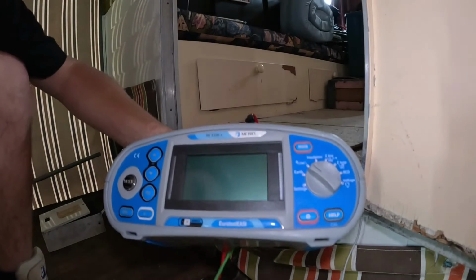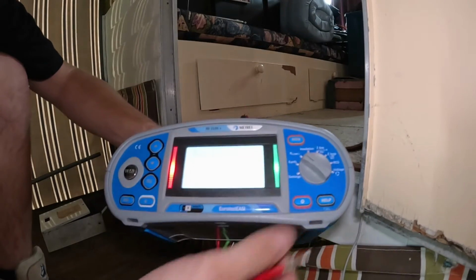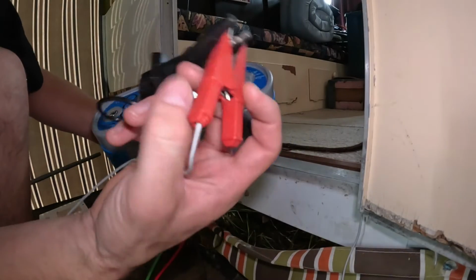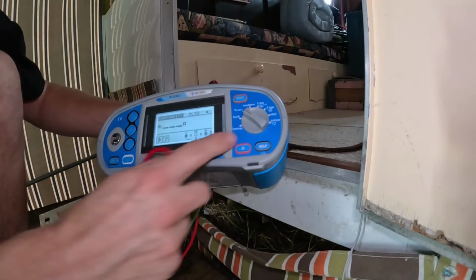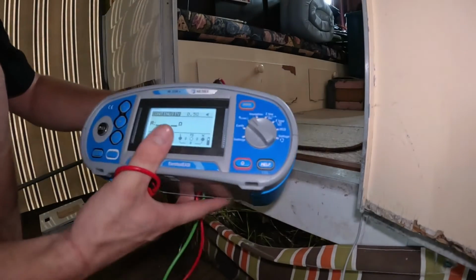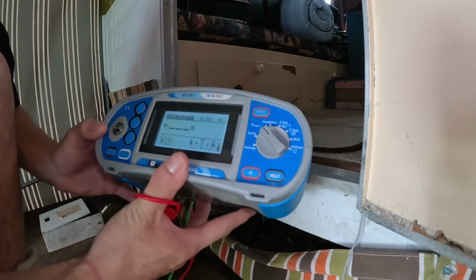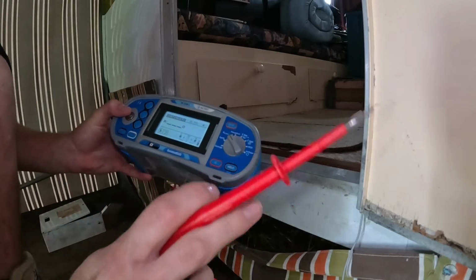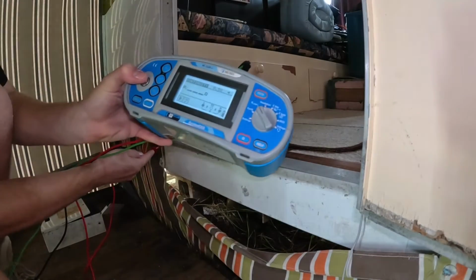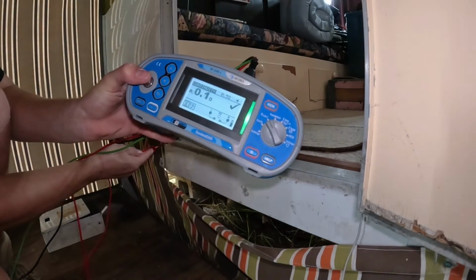Now, after the repair has been made, turn your meter back on, reconnect your lead to the switchboard, switch it to low ohms, do your calibration beforehand, and now touching the metal, there's a pass.